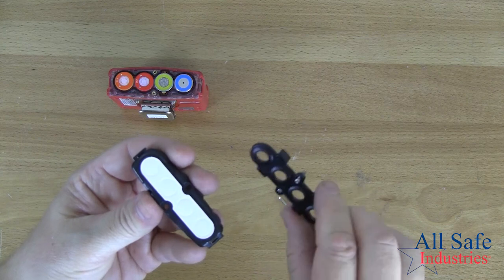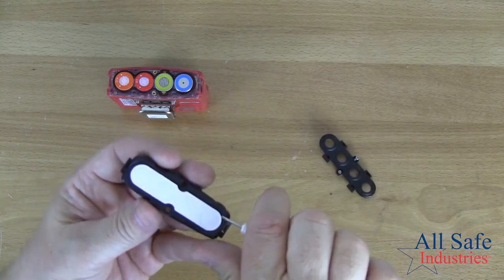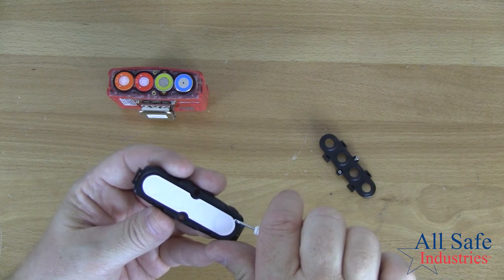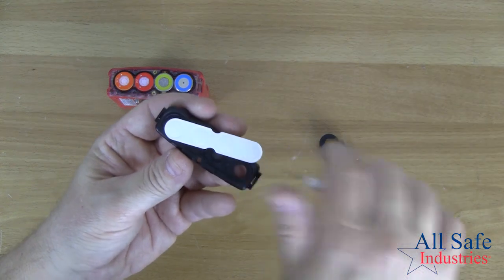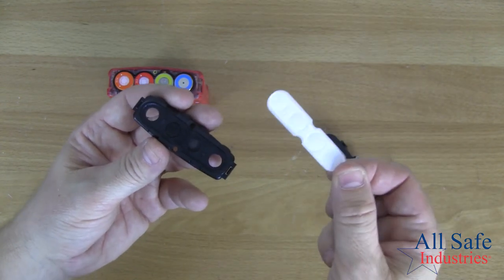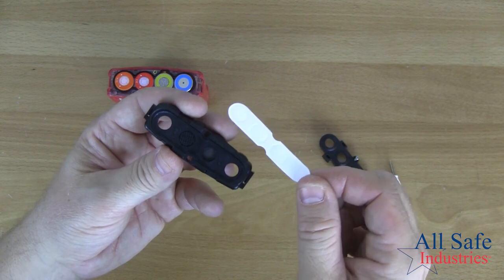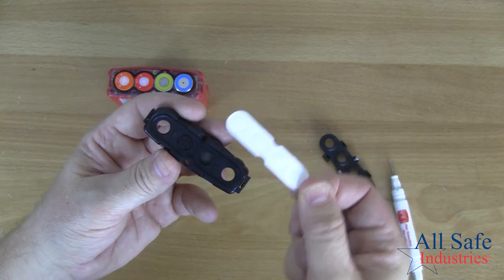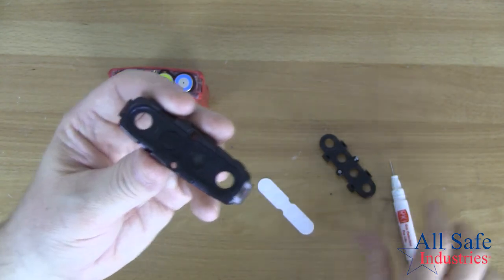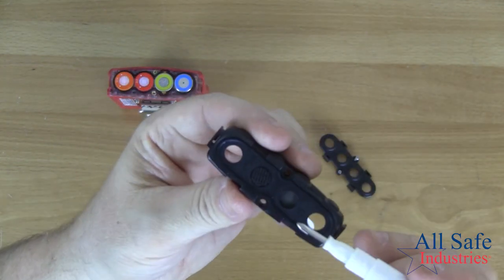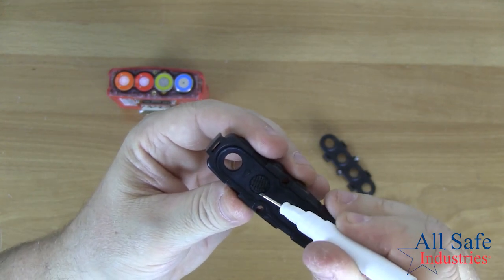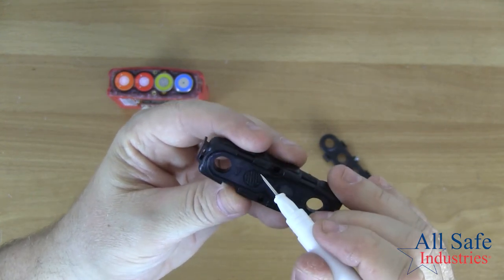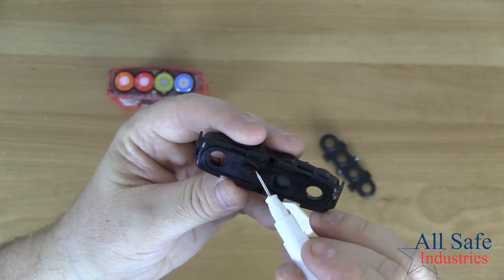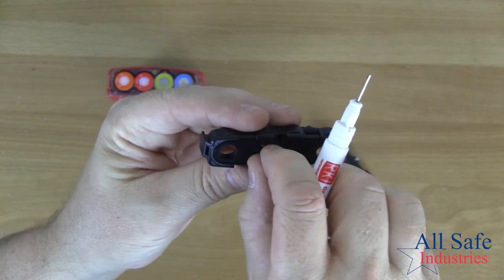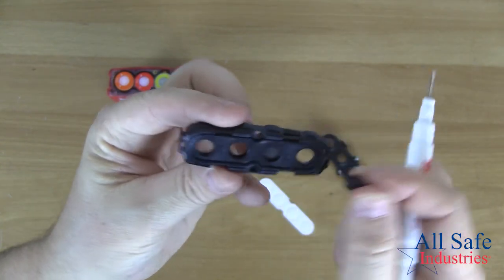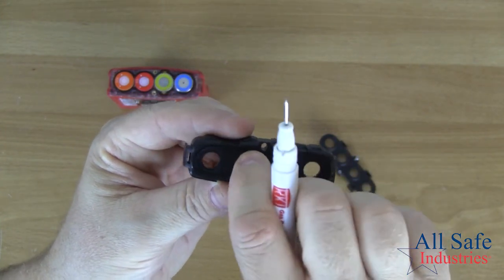So once we pull this apart, that just is our filter retainer. And then this is our hydrophobic filter. So hydrophobic means it's afraid of water, and the hydrophobic filter is what keeps the moisture and the water off our sensors. It's a gas detection instrument, so we need gas to get in, but we don't want liquid to get in. So there's our hydrophobic filter. And then there are a couple more filters inside here. This is an activated charcoal filter, and this goes over the CO sensor to help it from reacting to hydrocarbons. And so you'll see as I pull that out, it's just a little filter media, and it just sits right there on top of where the CO sensor sits.